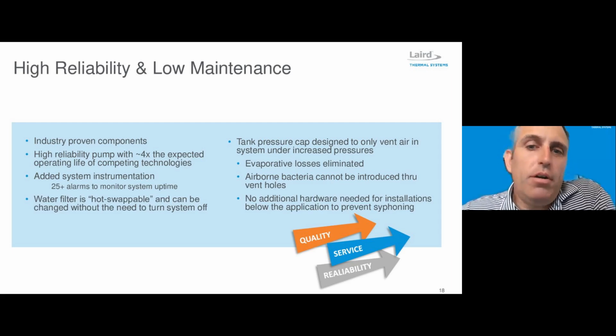Another important part of this system is that the hydraulic system has what's called a pressure cap on the reservoir. And so we call this a semi-closed system. A lot of the chillers out there in the market today have vented systems, and these are really easy to install and get up and running. But the downside is there's a lot of evaporative losses, and there's a lot of interaction with the environment in which it's installed. This can be dust, it can be biogrowth. And so what our system has is a pressure cap.